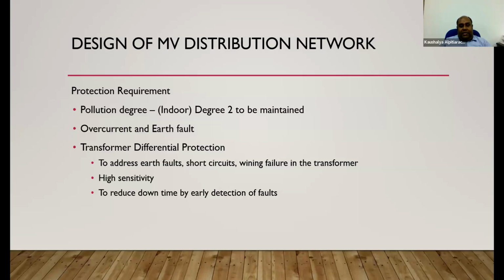Yes, protection requirements. Pollution degree. For indoor, we discussed that it is the degree 2 to be maintained. Overcurrent and earth faults, transformer differential protections. You know that in all the designs we see overcurrent and earth fault protection, but we rarely see transformer differential protection in the context in Sri Lanka. That's a very vital protection scheme and protection function, which can improve the lifespan of your transformer.